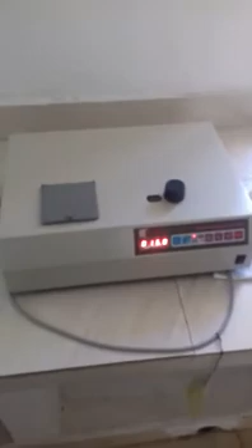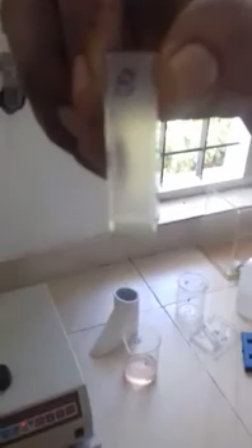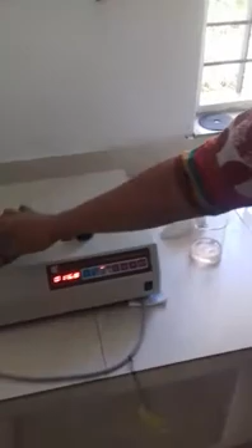You take a cuvette. This is called a cuvette. We fill the colored water in the cuvette, and by inserting it, we measure the absorbance. This is inside the spectrophotometer. You can see a space for inserting the cuvette. This is the place for setting the wavelength. For iron it is 510. You can see that it is 510.